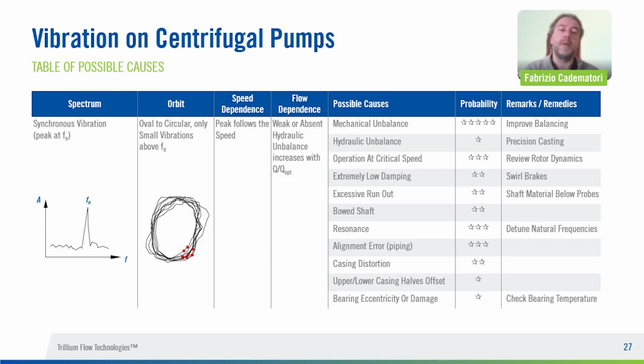Okay. To make our journey without losing our way, it is necessary to have a map. Our map is created by experience in the pump field. It is useful for the interpretation of vibrating behavior to use these elements. The number of stars that you see in the picture next to each cause is proportional to the likelihood of the problem occurring. We must understand that each vibrating source has its peculiar signature, which the vibration analyst must be able to recognize. In rotating machines, the most common symptom is synchronous vibration.